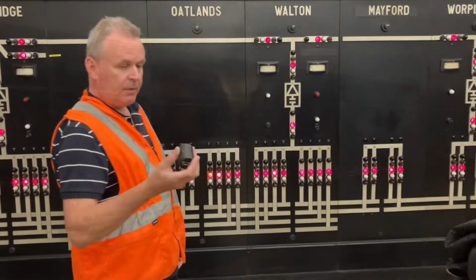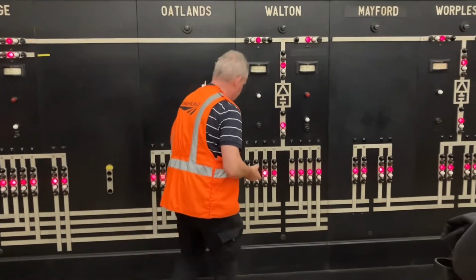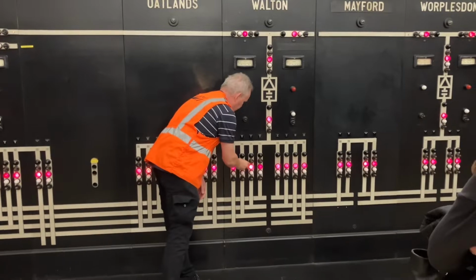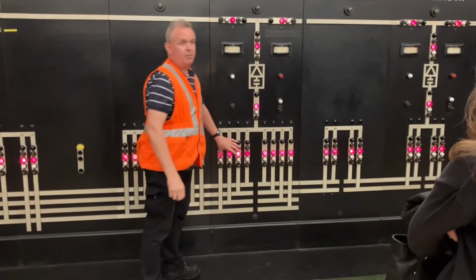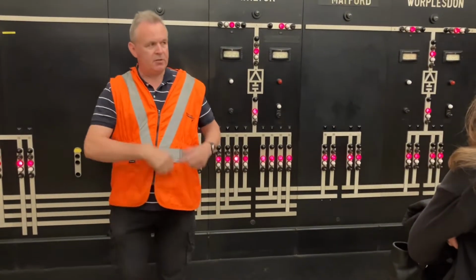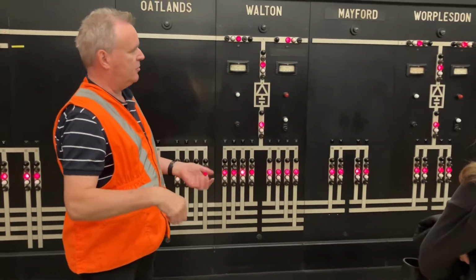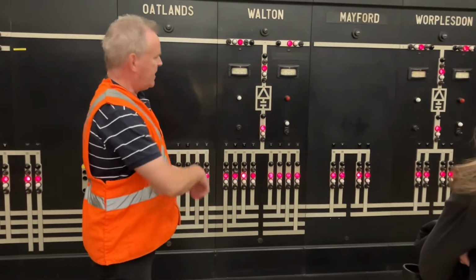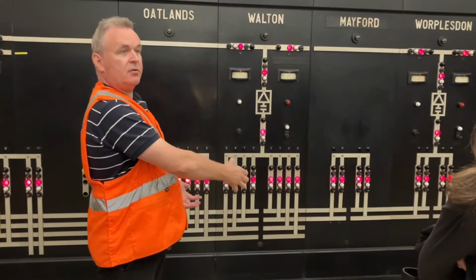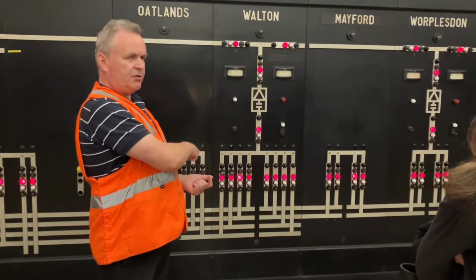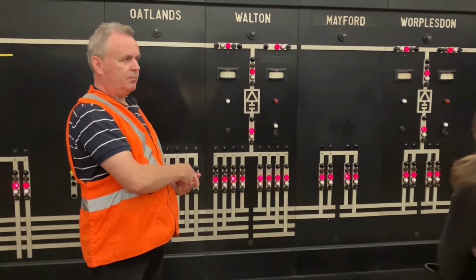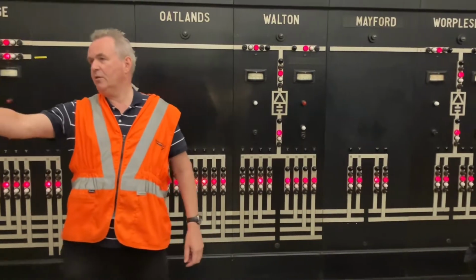We don't want different workers operating that once the breaker is open and people are working. We would then put the do-not-operate cap over the switch, which is a reminder for the electrical control operator that work is taking place, so they can't reclose that circuit breaker without agreement. You can see over there there's a form for that.